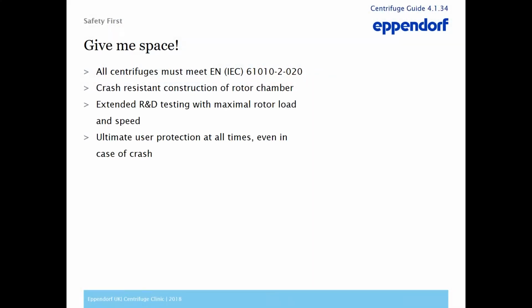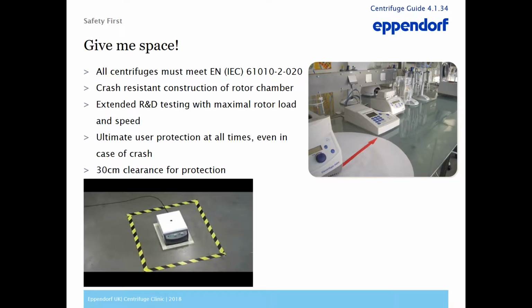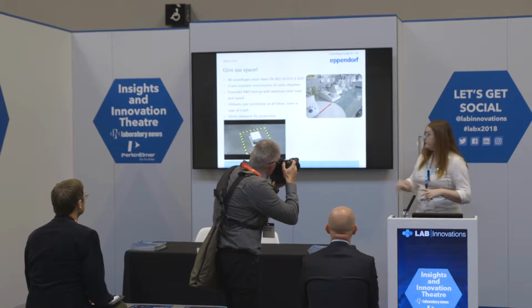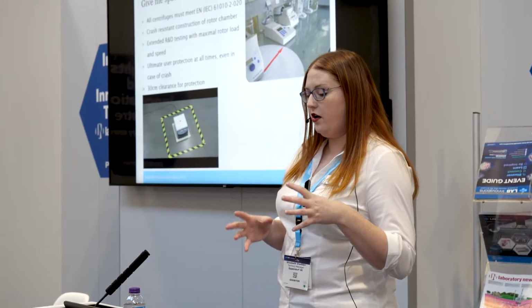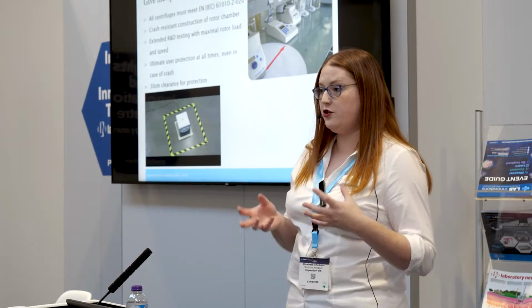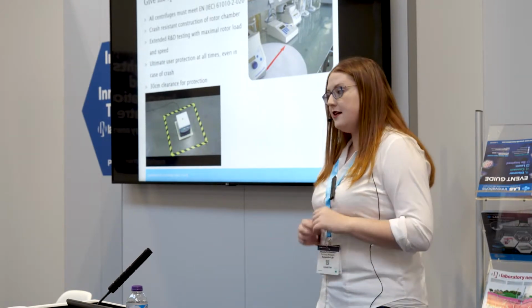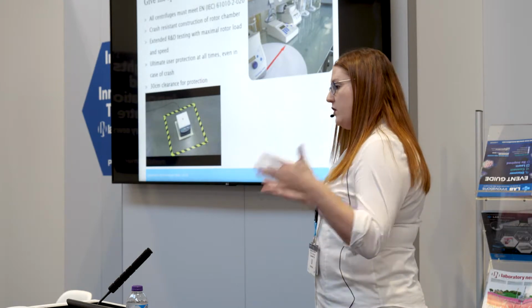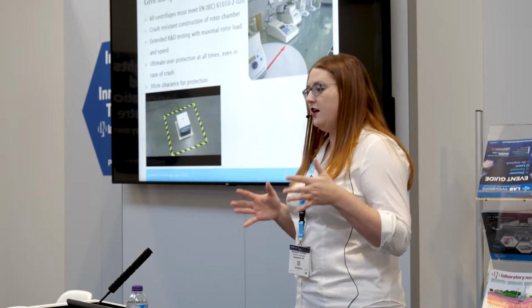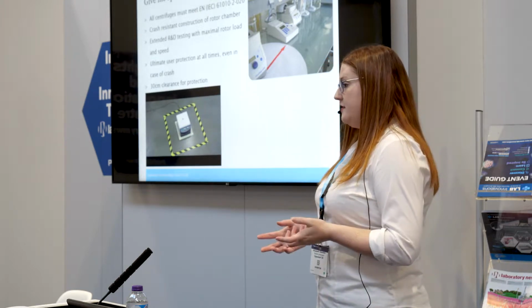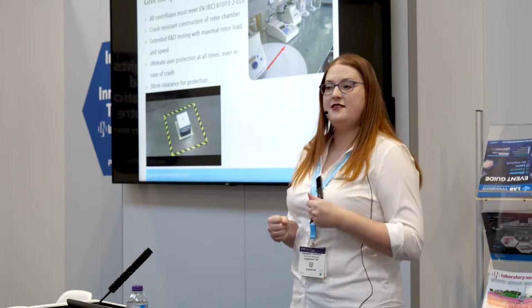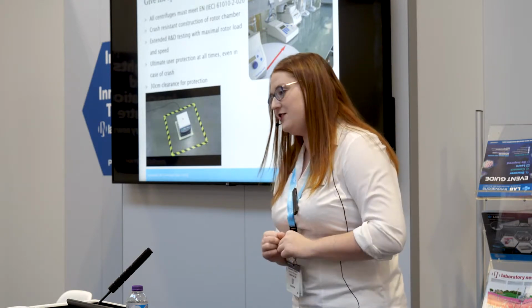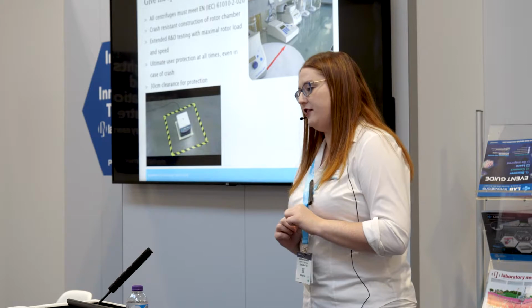So the first thing that we'll talk about is space. All centrifuges in the European Union have to conform to this particular regulation. This means that we have to actively crash our centrifuges, and we have to guarantee that our rotor chamber is crash resistant. What that means is when it crashes, the rotor has to be kept within the external box of the centrifuge, and the external box of the centrifuge can't move more than 30 centimeters. This is why in all the manuals we say, please leave 30 centimeters around your centrifuge, which is promptly ignored by everyone in any lab ever.